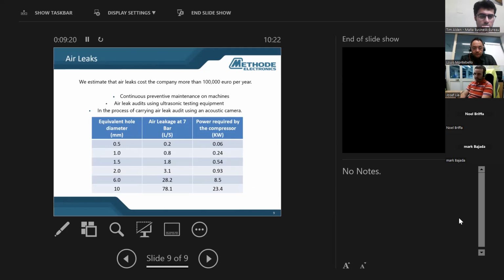Another energy saving area that we work a lot on is air leaks. For a large company like ours, air leaks are a continuous war. We calculate that we lose around 100,000 euro per year on air leaks. On the table, I am showing the kilowatts each air leak costs our company. To solve this, we continuously carry out preventive maintenance on equipment, especially during the low periods and weekends when production is low, so we detect more air leaks.